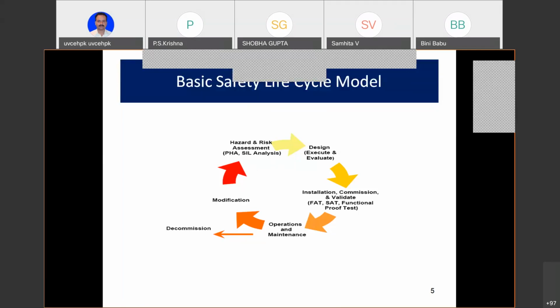So this SIL, don't get worried about SIL. SIL is nothing but a kind of safety performance indicator or statistical representation of the performance of safety. That is, when you want it, it will work. What is the reliability, etc. All that is built in there. Okay. Did we do that for that small plant? Hazard and risk assessment? Yes. Did we do a PHA? Yes. Still, let us pretend that we have done it.